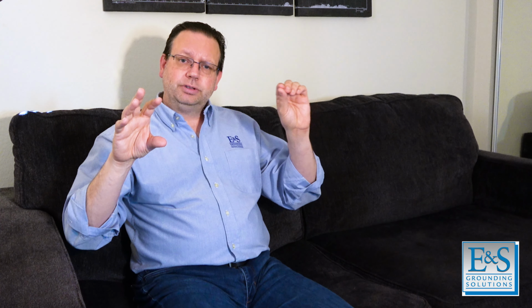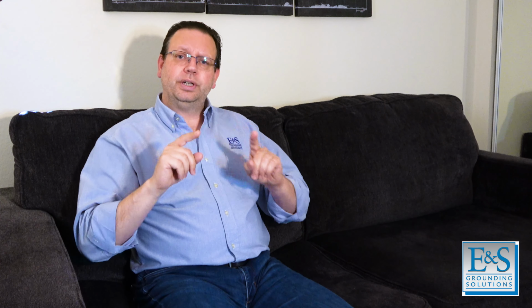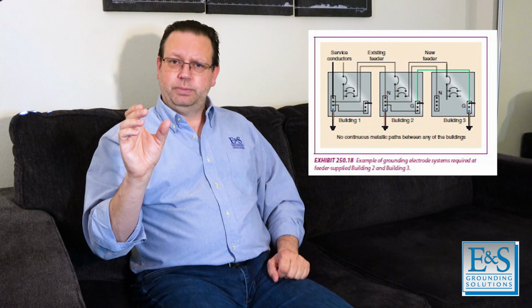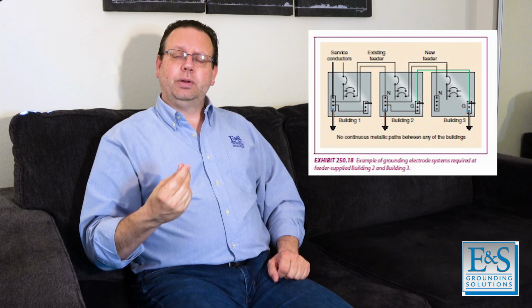If we recall, and I believe it's in 250.28, there's a discussion in the NEC about how to handle multiple structures being fed from a common feeder source, right, from a common circuit breaker box. And in certain cases, you have to prove that there's no metallic connection between the two structures. And in other cases, there is a connection between the metallic structures. And this is exactly what we're talking about.